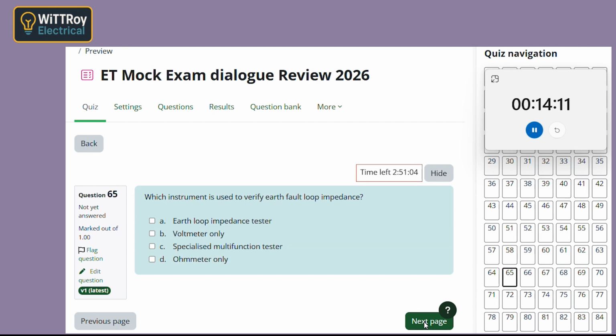Question 65. Which instrument is used to verify earth fault loop impedance? I think I chose voltmeter. Yeah, a lot of people go for that, but it's not right. This test is a bit more involved. What we're trying to check is whether enough fault current would flow if something went wrong. So, like if active touches earth?